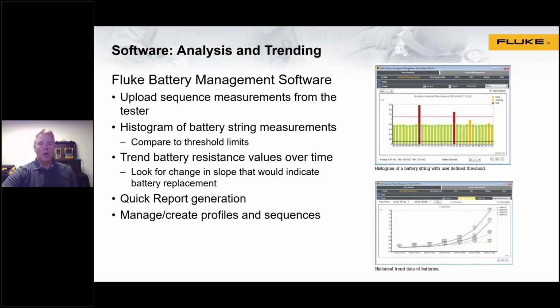Another way of using this is that trend, which is so important over time. That's what our lower graph is showing, on a battery by battery basis, that trend of resistance values. What you'd look for there is that more dramatic change in slope, which is very indicative of a battery that is experiencing one of the failure modes that we discussed earlier. And of course, the software can help manage and generate reports. Essentially, you can say what you want included in the report and then generate that hard copy output, as well as creating profiles and sequences that can be loaded into the tester.